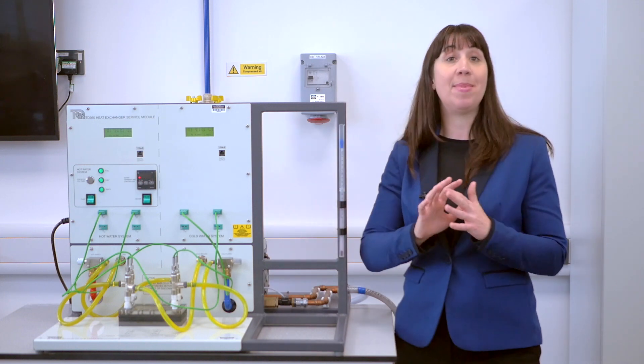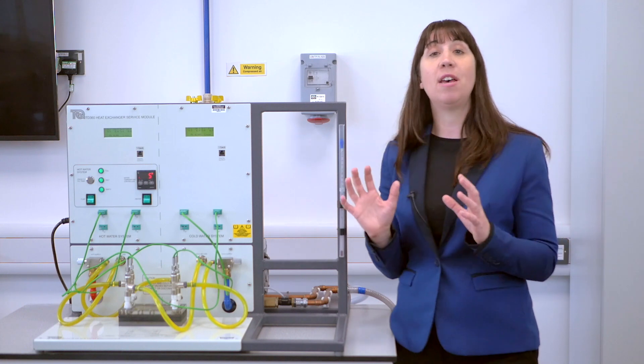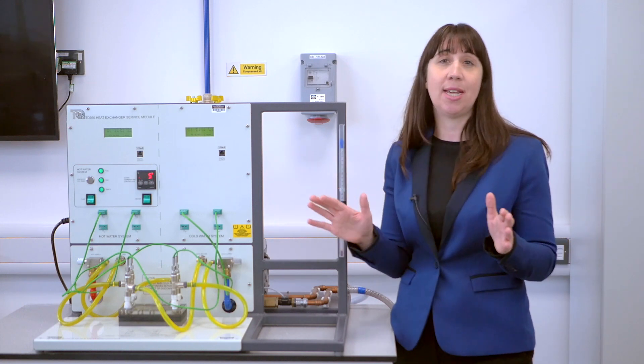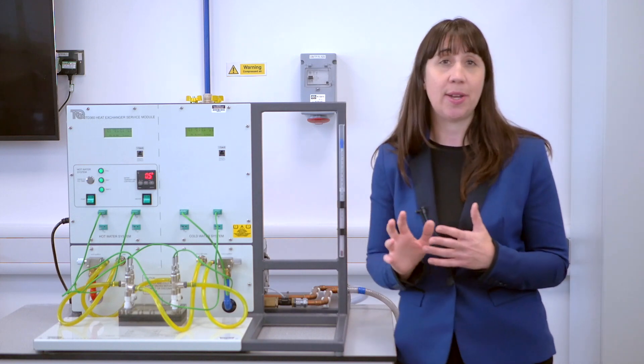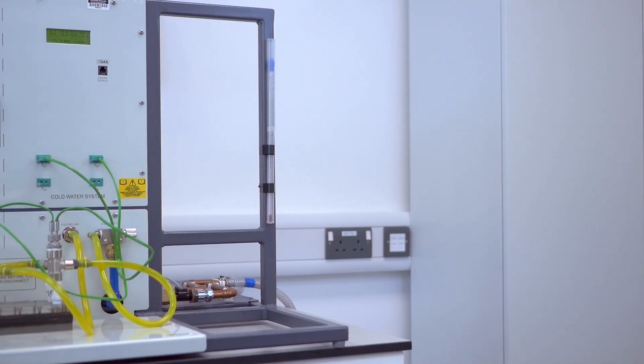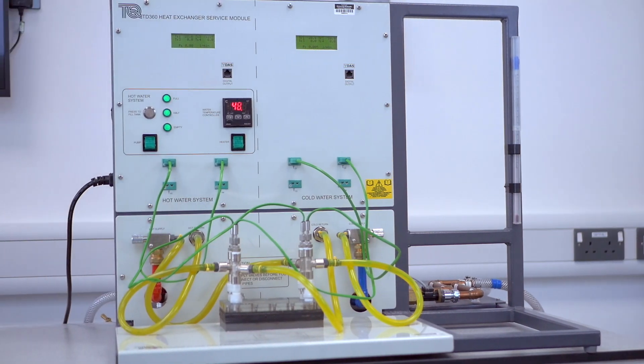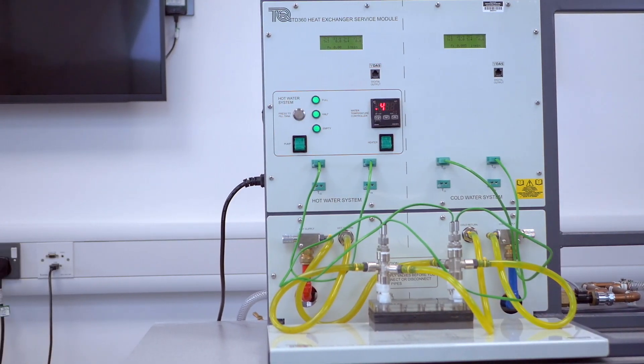To protect against the water becoming dangerously hot, there's a thermostat that will cut off power to the heater when the temperature rises beyond approximately 68 celsius. This can be quickly reset once the water temperature is at an acceptable level allowing students to return to their studies.